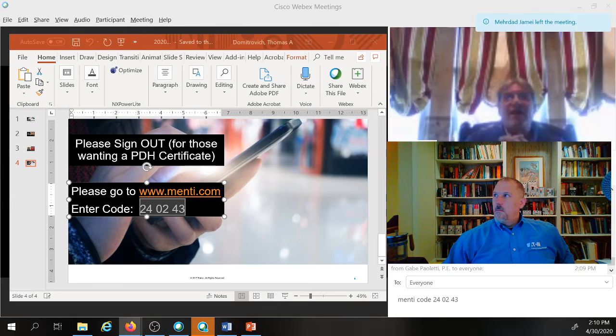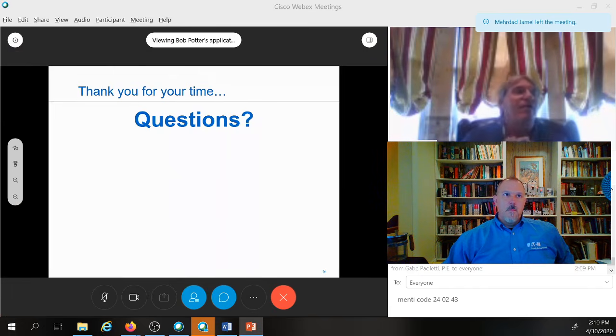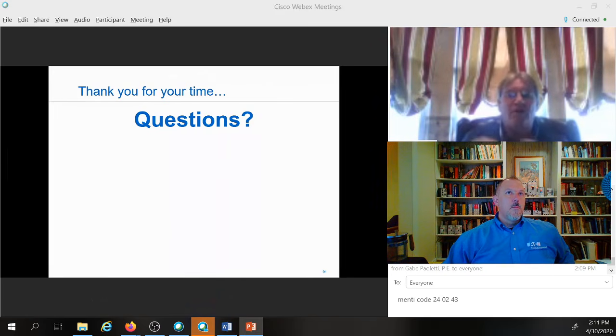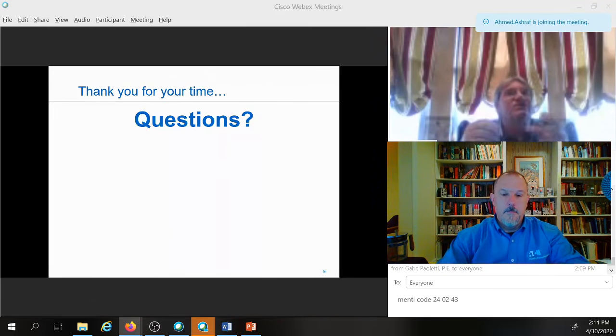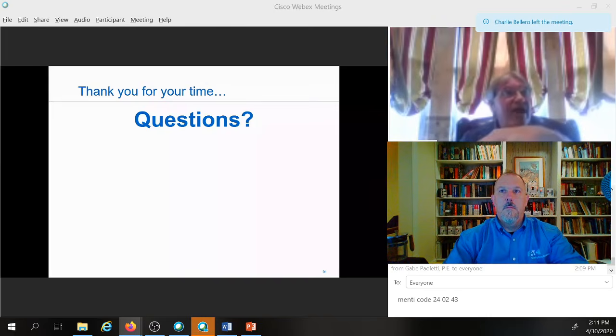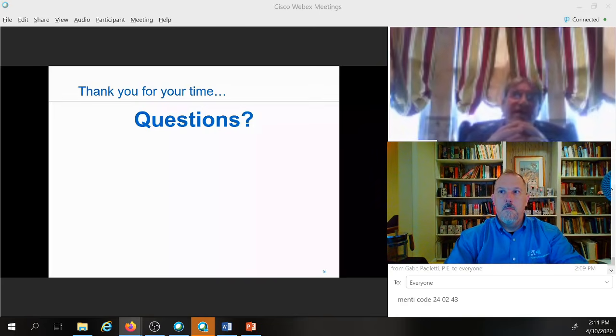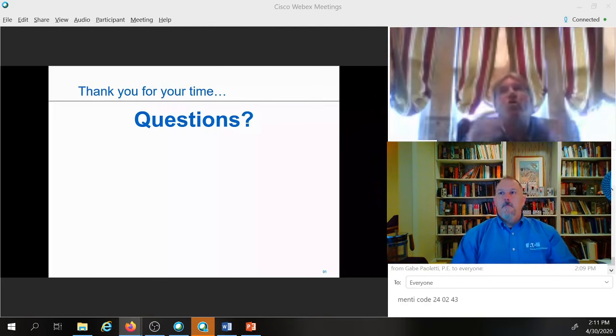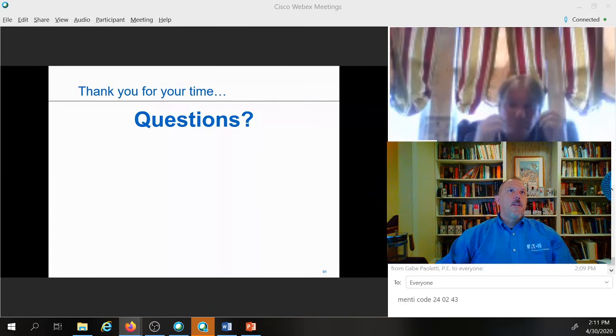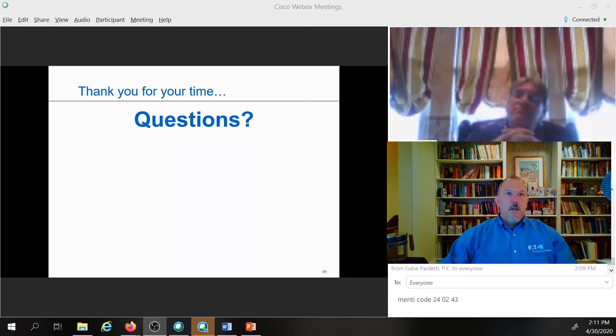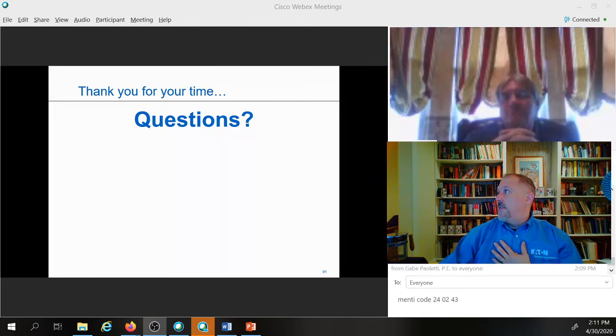So that's why, in areas with Group G, a portable floodlight that can be taken into those areas may have restrictions on how high you can point it upward. If the dust, which could deflagrate, and I think some of those are the types of dust you would see in a brewery, sits on that lens where the heat is coming through for the illumination, it's going to get extremely hot and could cause the dust to catch fire. I think what we will have to do is go do some investigating at a brewery.